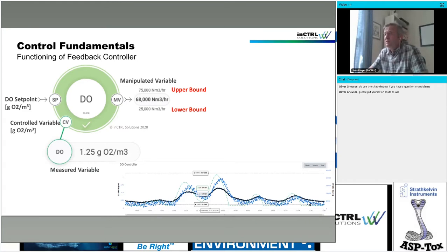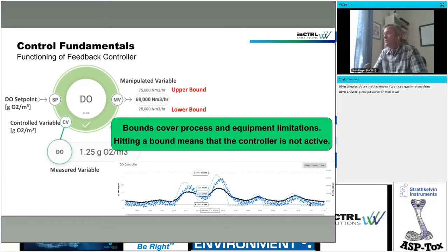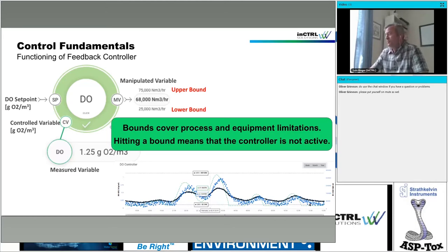What we typically do is plot the set point and the control variable on the left-hand side — they have the same unit — and on the right-hand side, the manipulated variable and the controller bounds. Very important: if you are hitting a bound, the bounds are there to protect your process and equipment. If you are hitting a bound, your controller is actually not doing anything. It's just sitting in the box. So if you check the controller performance and you are hitting a bound, that controller is not active at all.